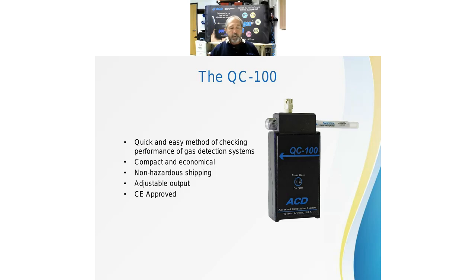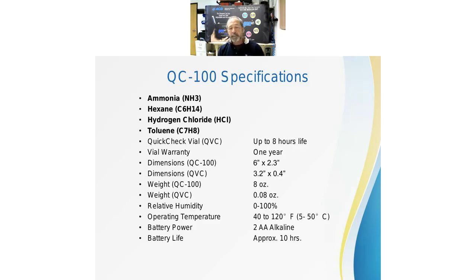That's our adjustable output. This one is CE approved as well. And it does the same gases and the same principle of operation. A lot of our customers use these for fence line monitoring. Along the edge of their facility, they can't pollute out X amount of, say, toluene past their fence lines. So they've got an employee that walks along that fence line with this thing running, and he hits a sensor, one sensor, next sensor, and functionally tests the entire system.